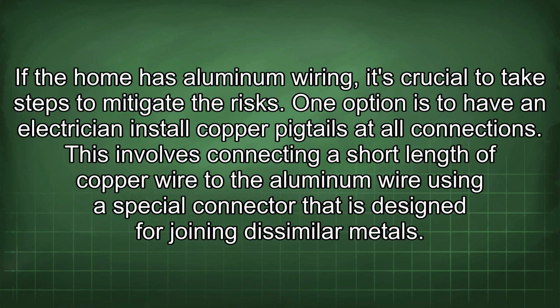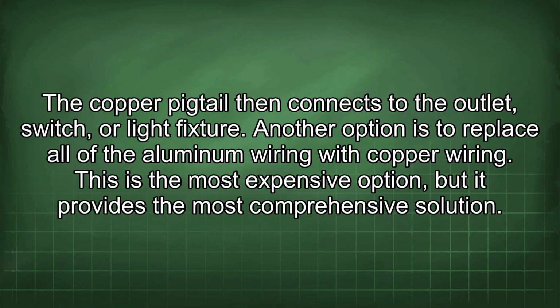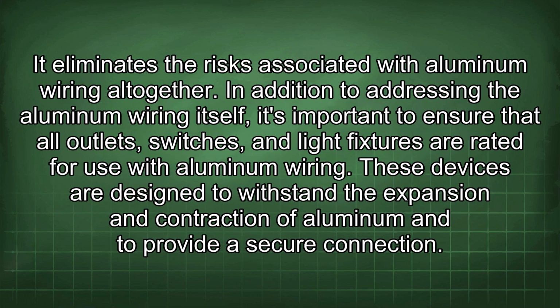If the home has aluminum wiring, it's crucial to take steps to mitigate the risks. One option is to have an electrician install copper pigtails at all connections. This involves connecting a short length of copper wire to the aluminum wire using a special connector that is designed for joining dissimilar metals. The copper pigtail then connects to the outlet, switch, or light fixture. Another option is to replace all of the aluminum wiring with copper wiring. This is the most expensive option, but it provides the most comprehensive solution. It eliminates the risks associated with aluminum wiring altogether.